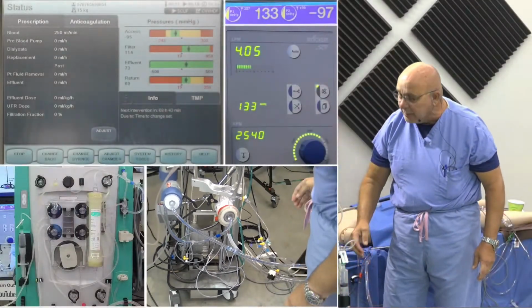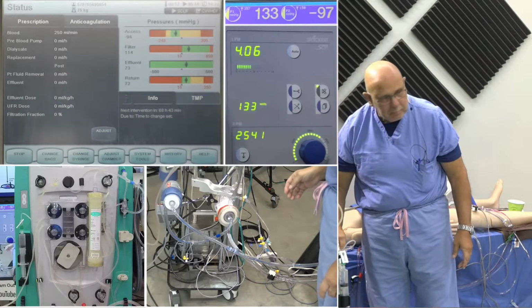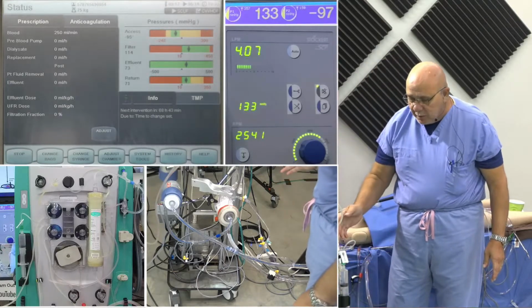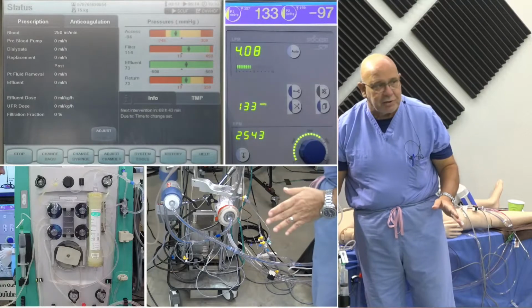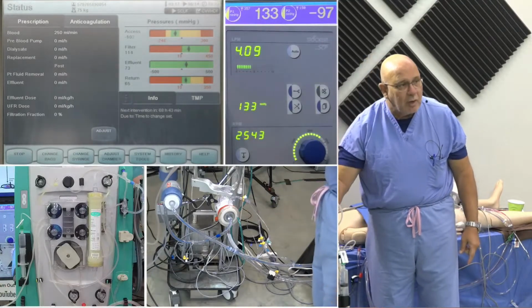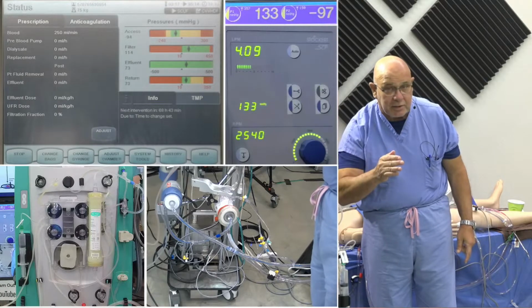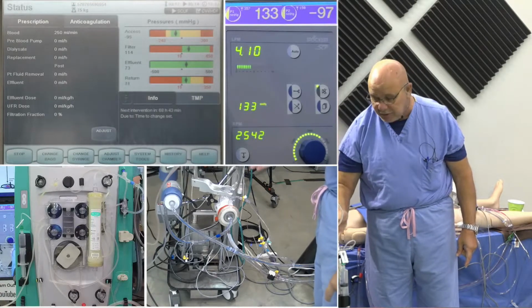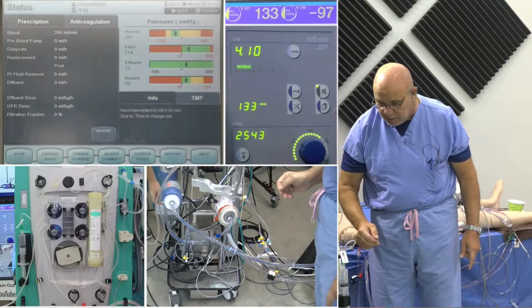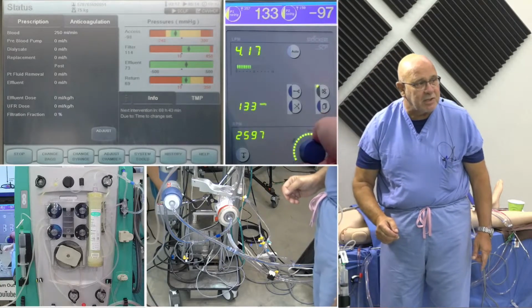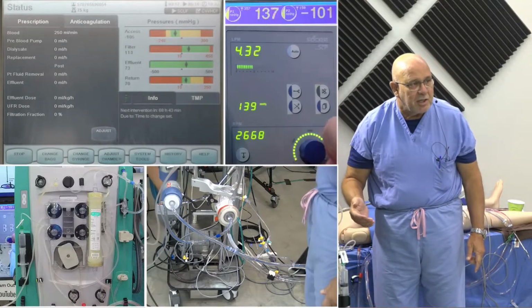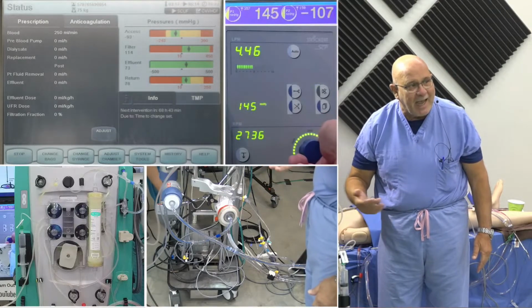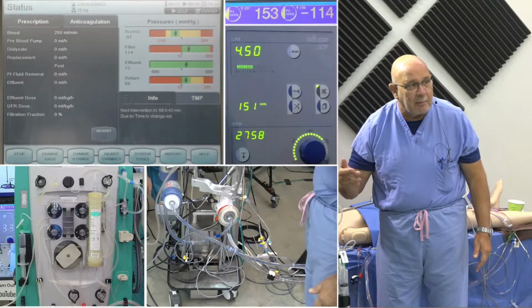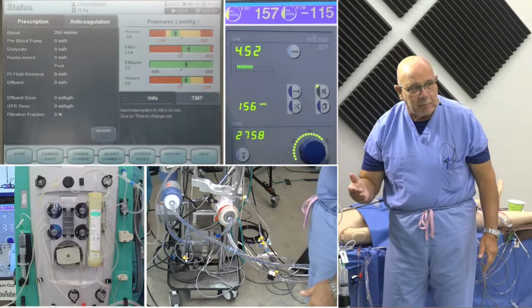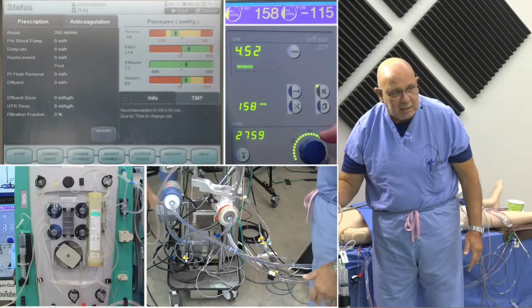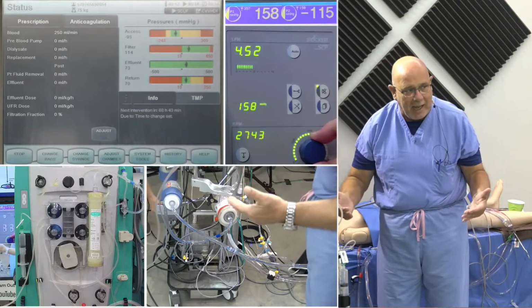That's great. And hey, Magic, could you help me out and turn some dials? So what we're going to do is, just watching the pressures of the ECMO circuit, we're going to increase the flow from 4 liters a minute to 4.5 liters per minute. So go ahead and do that. To 4.5, yeah, it's not going to be a big change. But watch the pressures. You see immediately the access pressure is going more negative, and the return pressure, of course, went more positive. You expect that to happen.